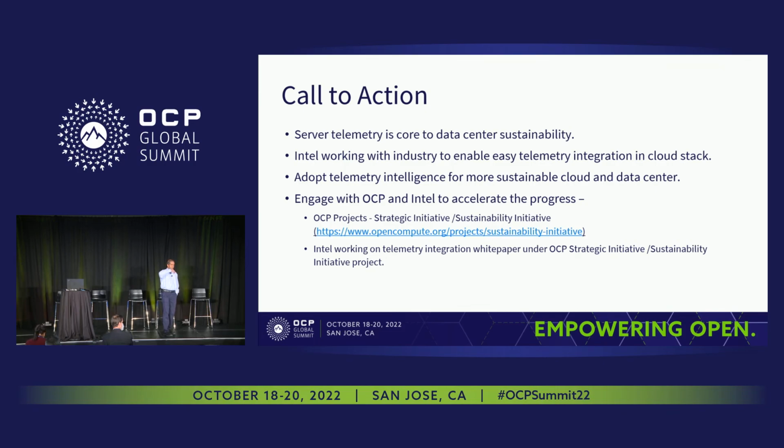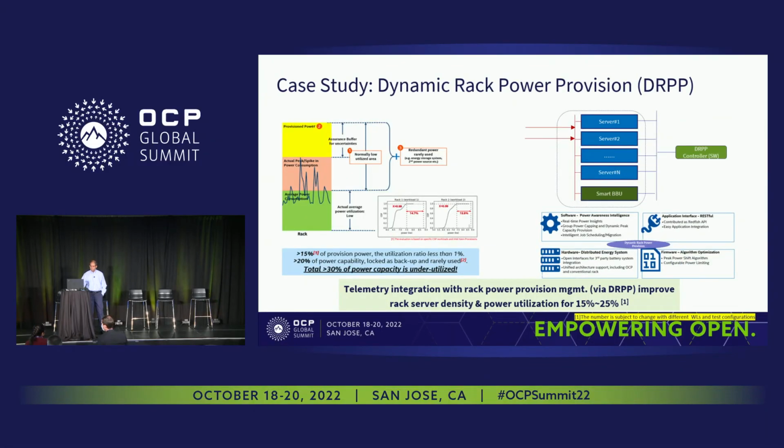So he's asking if you're collecting power data on this chart, and yes, we are. Not only are we collecting power, we're also predicting the workload and how it is going to behave. We know when the workload comes in, it typically uses this level of power, because we don't want to wait till the workload starts ramping up and then find out that we have a power problem and start trying to clamp it. So we predict what's happening at the workload level, and we're also measuring the power. Between the two, we're able to keep this under a given power budget.